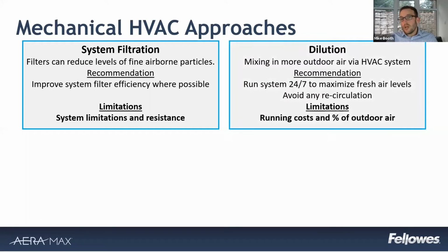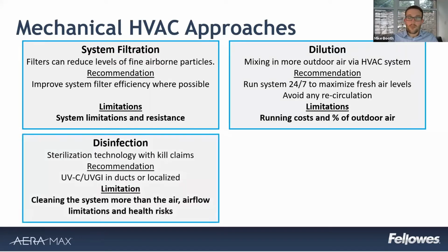Secondly, dilution, and this is ultimately increasing the amount of air that's being provided. Again, that term fresh air, but ultimately this is outdoor air that we're talking about. As much as possible, avoiding recirculation. But again, from a sustainability perspective, this is a significant increase to the running costs, and there can be limitations depending on the system design, just in terms of how much percentage of outdoor air you're able to introduce based on your own system setup.